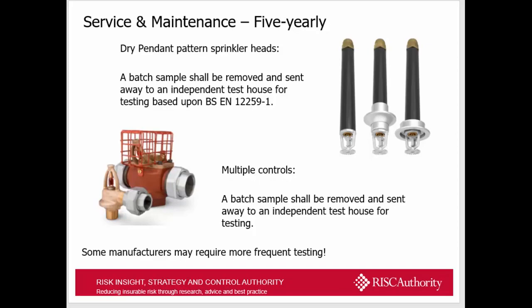They're largely covered in TB 203. They're covered in Technical Bulletin TB 213. But the requirement still is every 5 years a batch sample is removed and sent away for independent testing. However, it also depends on the manufacturers, because they may require them to be sooner than every 5 years.